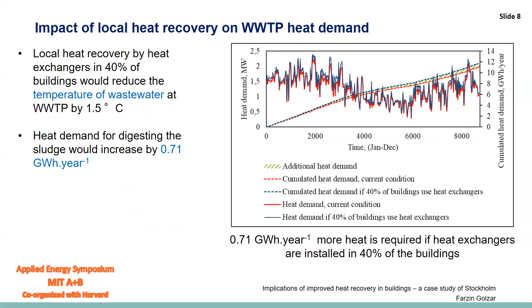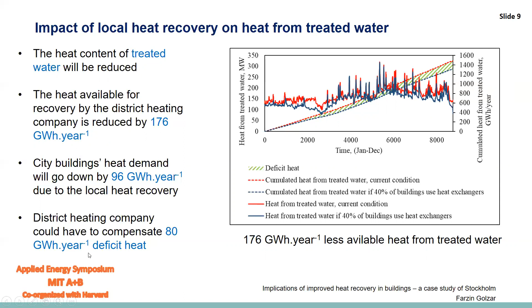Moreover, the amount of available heat for recovery at the district heating company level would be decreased. In this figure, a red line shows the amount of available heat for recovery in treated water by the district heating company in the current condition. But in the case of local heat recovery, 176 gigawatt hour per year less heat is available for heat recovery. But on the other hand, local heat recovery would cause 96 gigawatt hour less heat demand in buildings. So generally, the district heating company may need to compensate an 80 gigawatt hour per year deficit of heat.